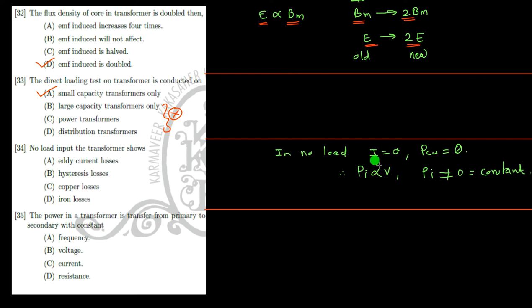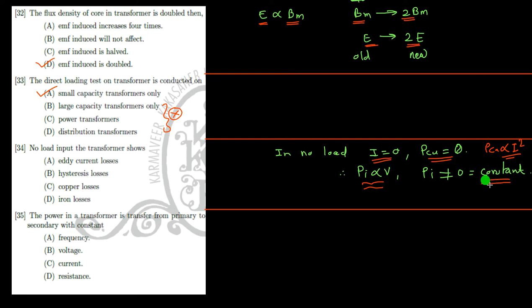No-load input of the transformer shows iron losses. Under no-load, secondary current is zero, so copper losses are zero because copper losses are proportional to the square of the current. Whatever the primary-side wattmeter shows is nothing but iron losses, since iron losses are proportional to voltage and remain constant irrespective of load current. Iron loss is the combination of eddy current and hysteresis losses.